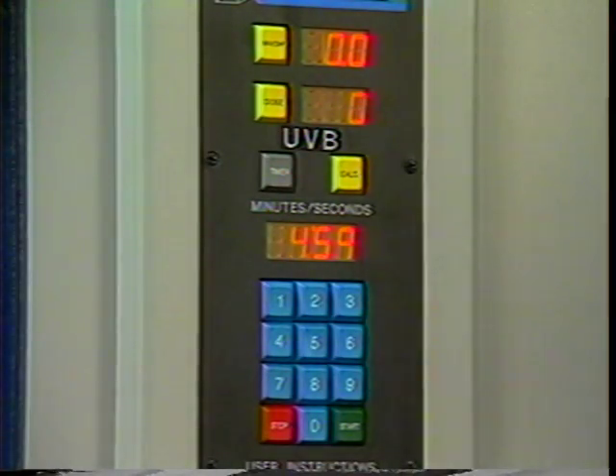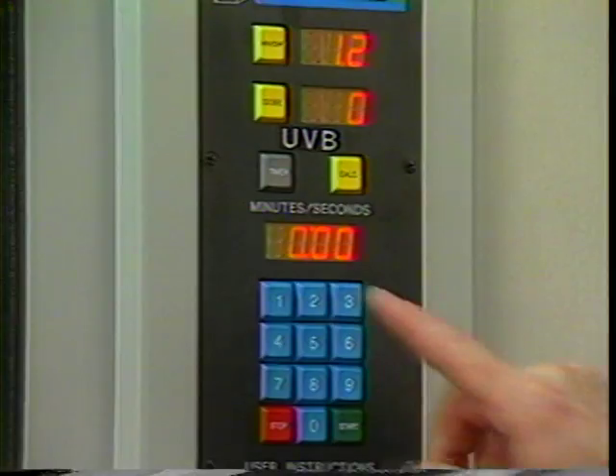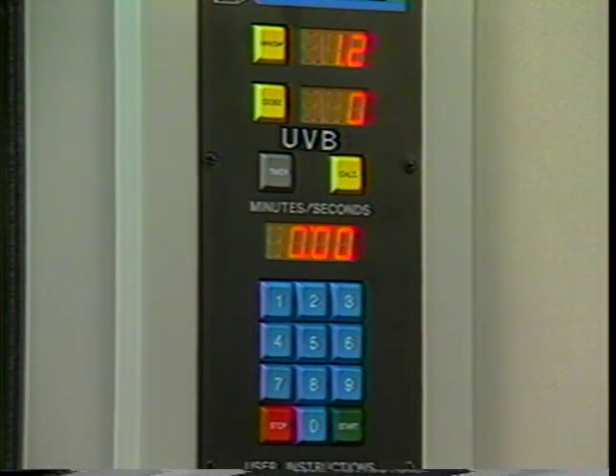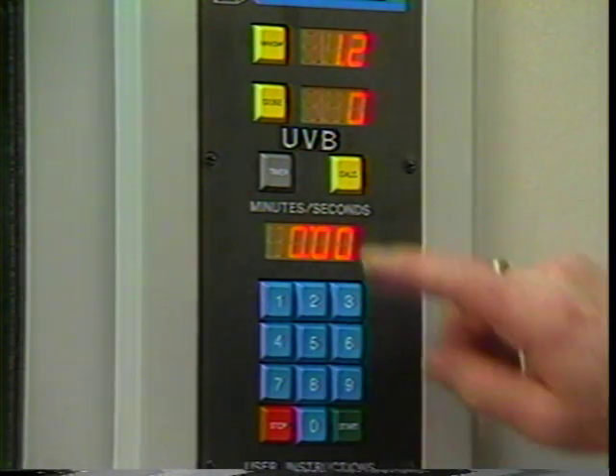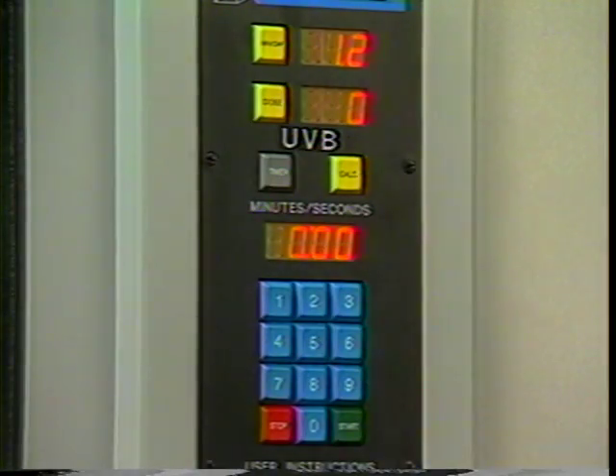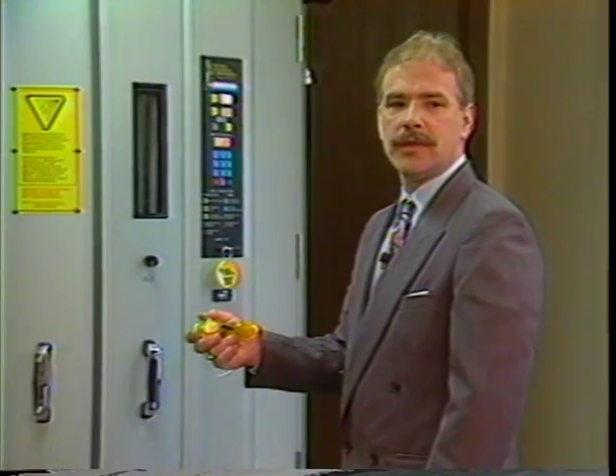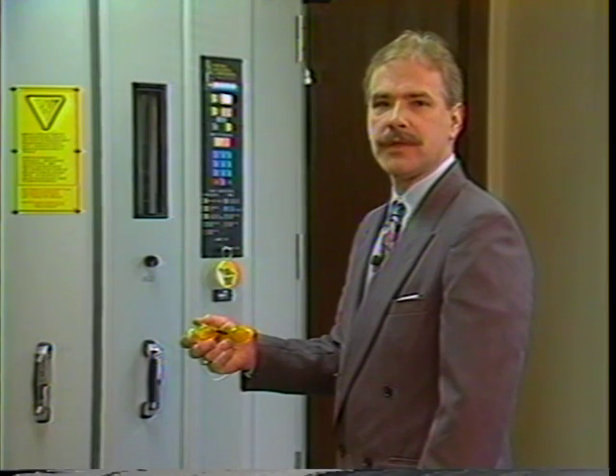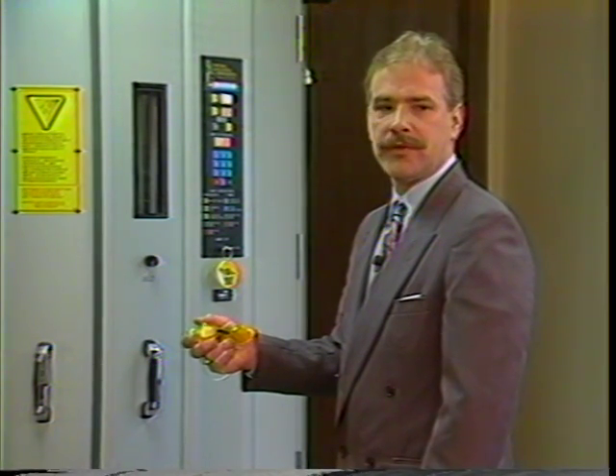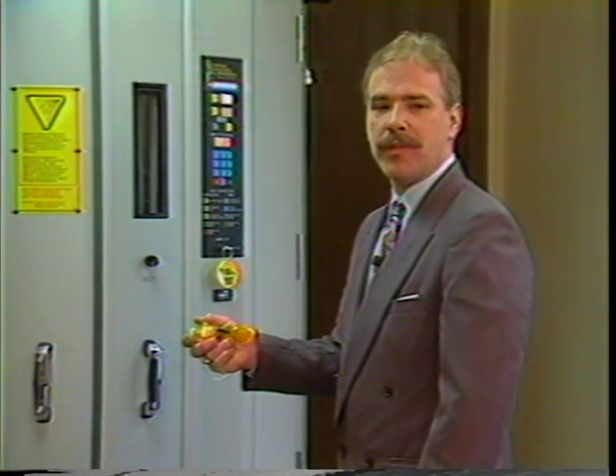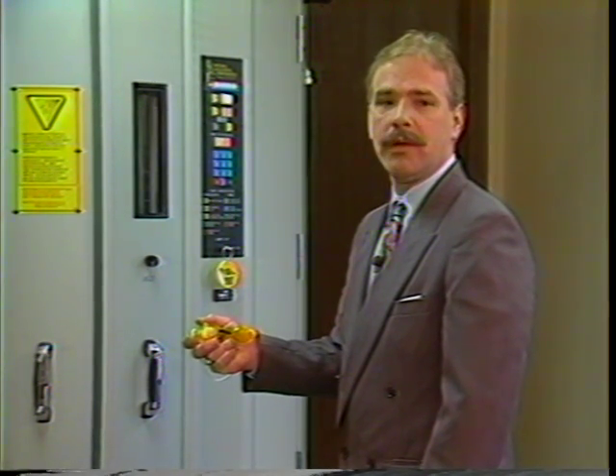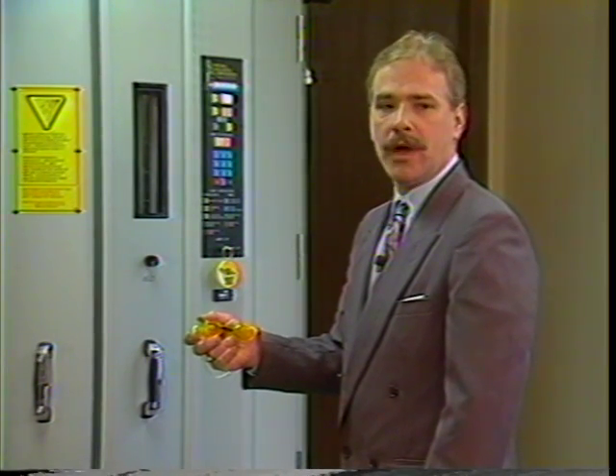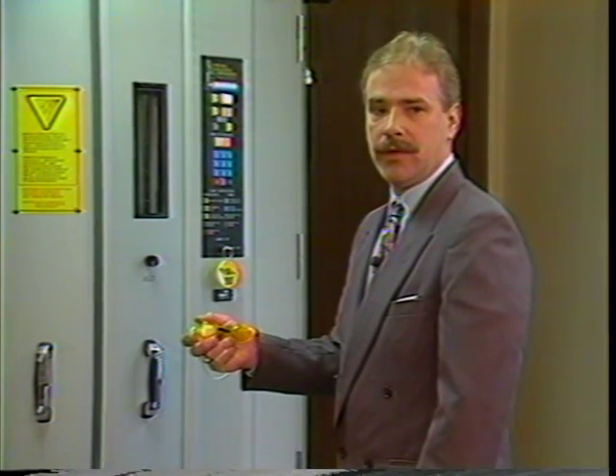So far in this discussion, we have reviewed proper techniques for warm-up of the device, correct measurement of lamp output, entry of the information into the memory of the PhotoSense timer, and entry of dosage information into the timer as prescribed by the physician. When you're ready to begin patient treatment, be certain the patient is wearing the UV blocking goggles to protect their eyes. The goggles from National Biological Corporation are non-UV permeable so the patient can see out with virtually no distortion. Have the patient don the goggles and step into the center of the unit.